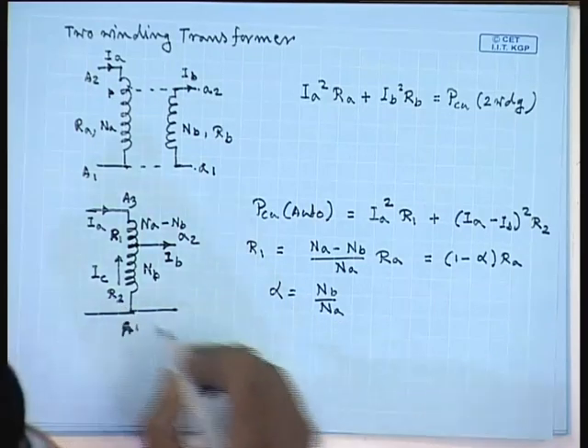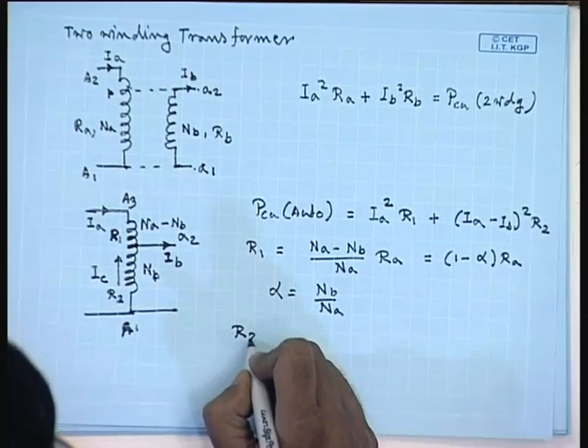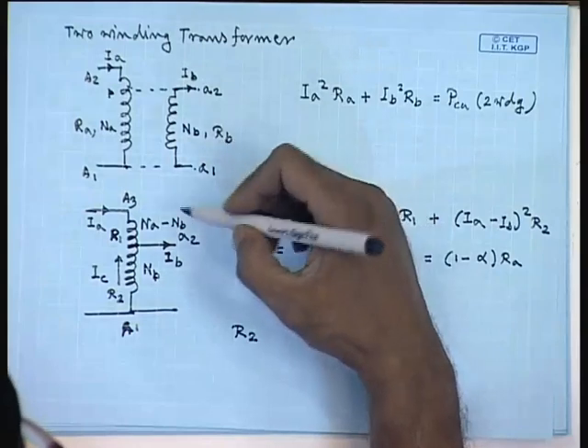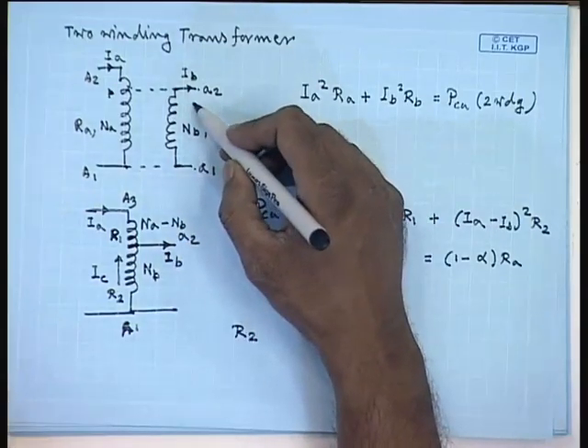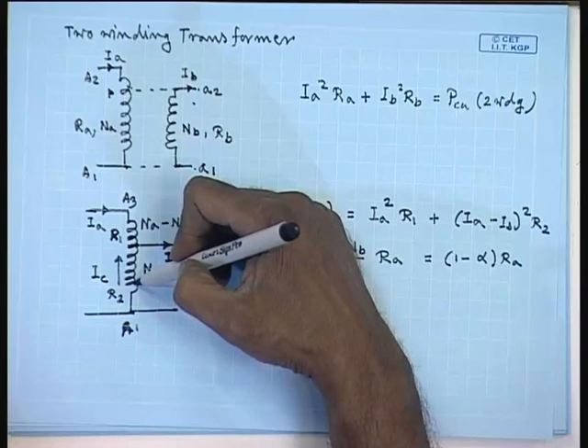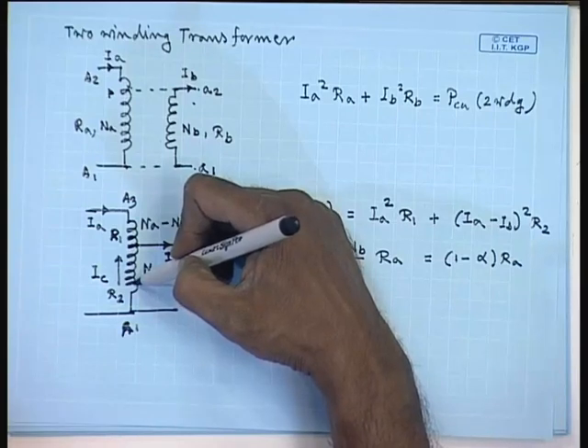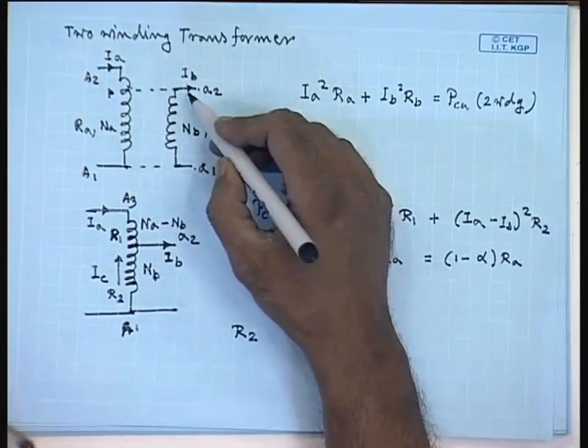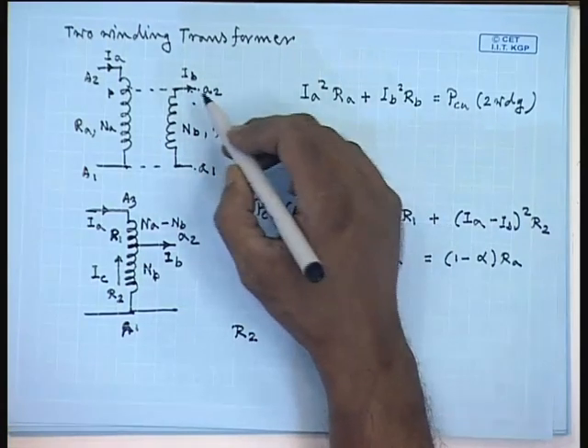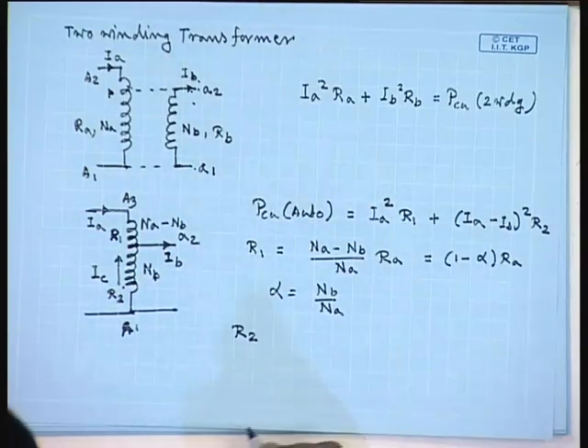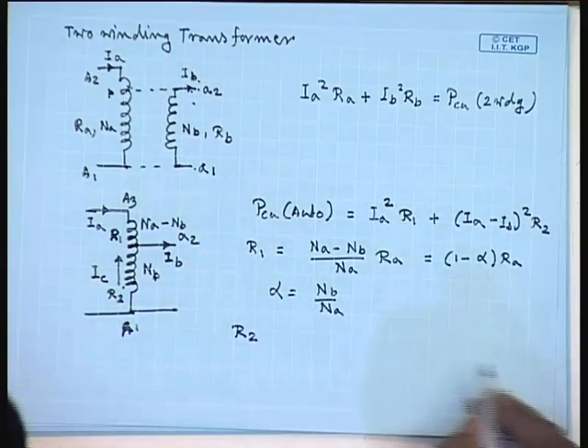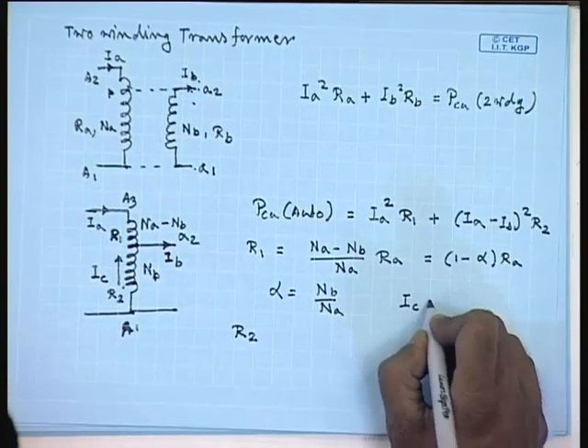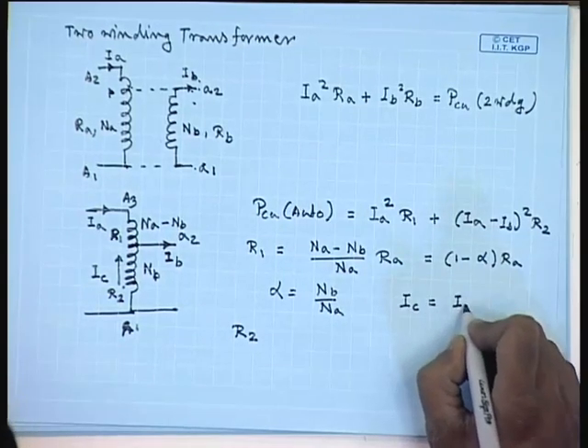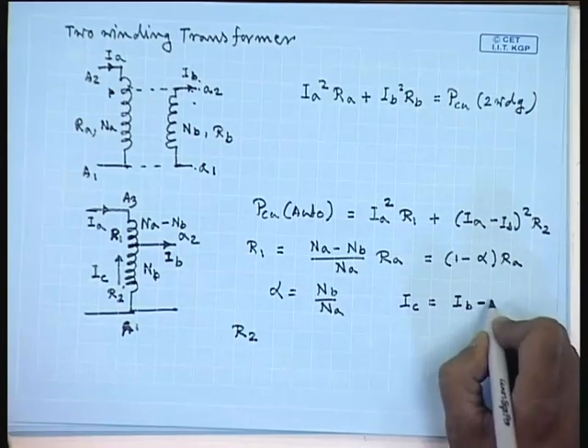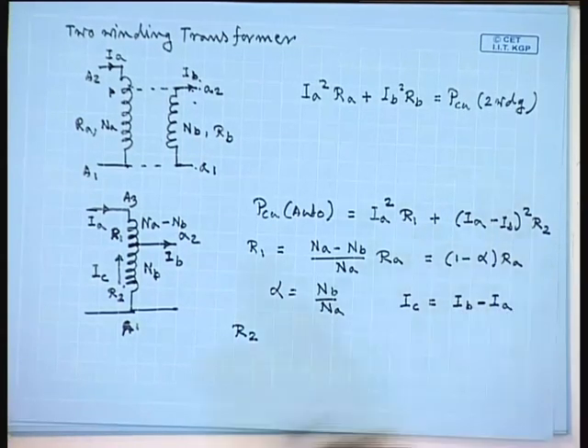To calculate the resistance R2, we note that the number of turns of the LV winding of the two winding transformer and the number of turns of the lower part of the auto transformer are the same. However, while the current in the LV winding is IB, the current in the lower part of the auto transformer is IC, where IC equals IB minus IA.